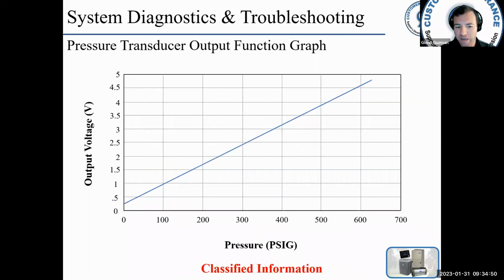Now, there is an output function graph. You will not find this graph in the manual, so you can use it here. Remember, it's 5 volts DC being supplied to the pressure transducer. So let's say I've got a pressure of, call it 150 psig. I'm going to go right here, that's give or take around this area, and I'm going to follow it over to the left. What would you say? 1.3, 1.35, somewhere in there. So I should have 5 volts DC to the sensor and get back around 1.3, 1.35. That's at a pressure of 150. As the pressure changes, your voltage is going to change as well.